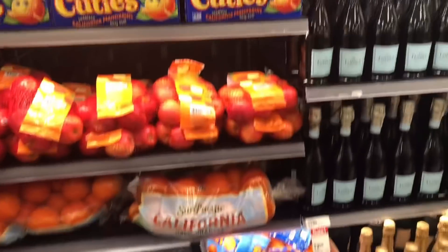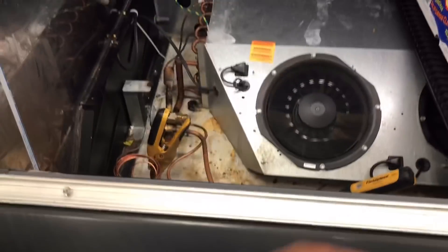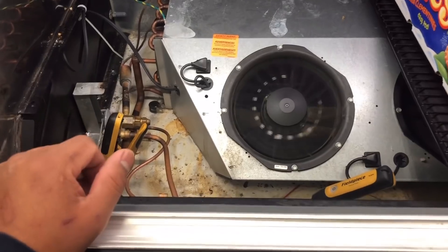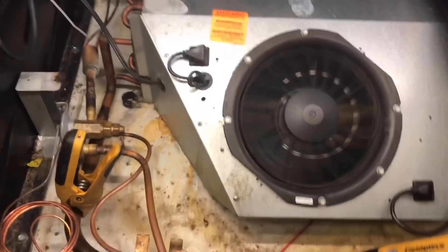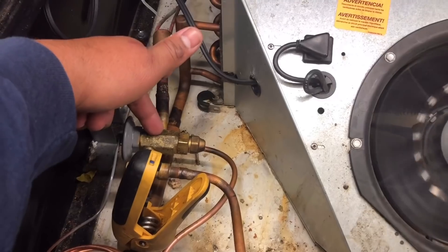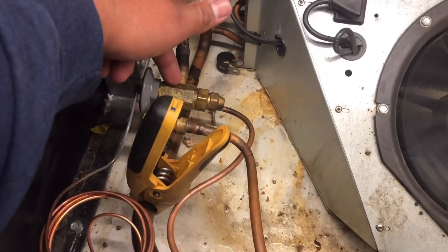Alright guys, we're back at the case running about 38 degrees. I got a hold of my co-worker. Essentially what's happening is this EPR valve right here - they put the red powerhead on it - the EPR is opening up 100%, which is essentially making this valve appear way too big.